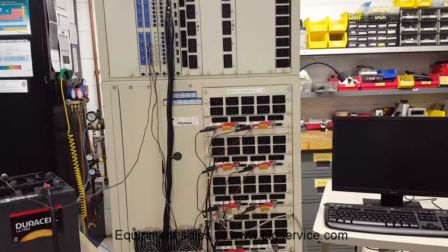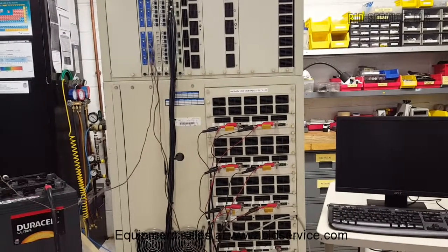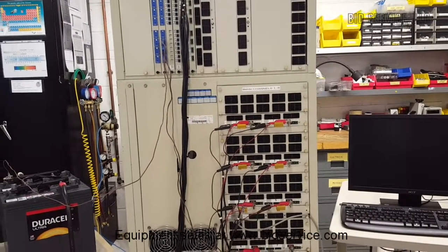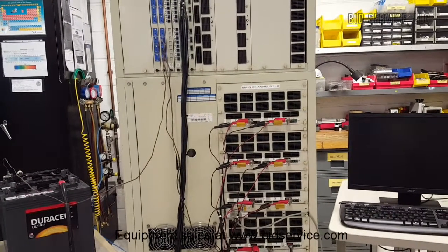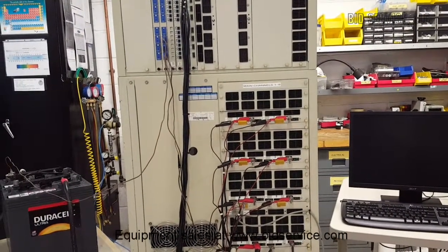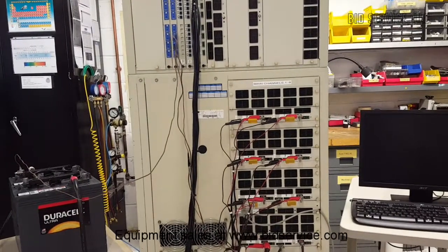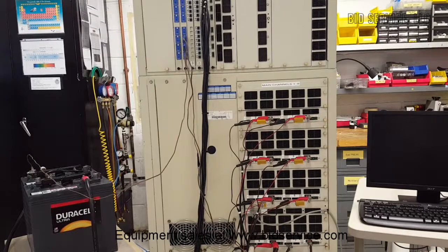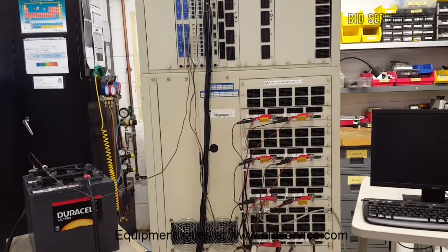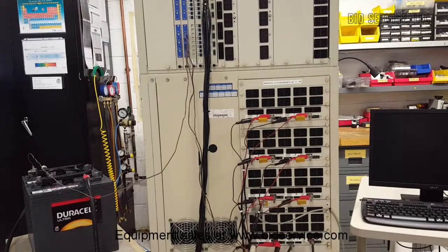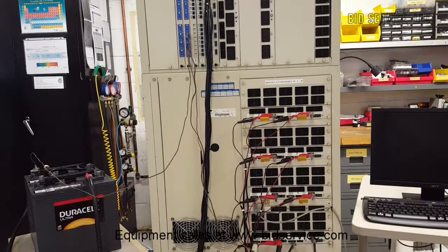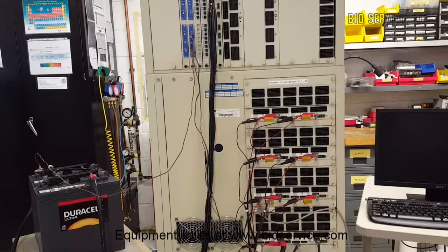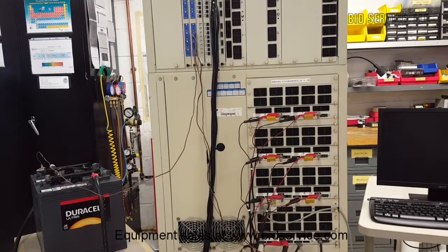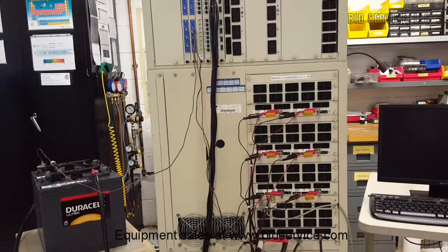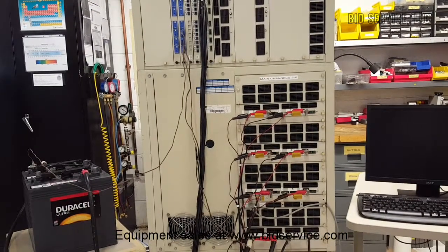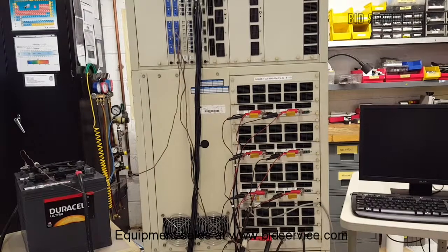A demonstration of the Arbin Instruments BT2043 battery test system. It is a computer-controlled battery test piece of equipment designed for research and development and for the production of batteries and any energy storage device. The system is powered by 208 volts 3-phase, requiring a 42 amp service. It has a voltage range from -1 to +100 volts, and a current range of up to 25 amps.